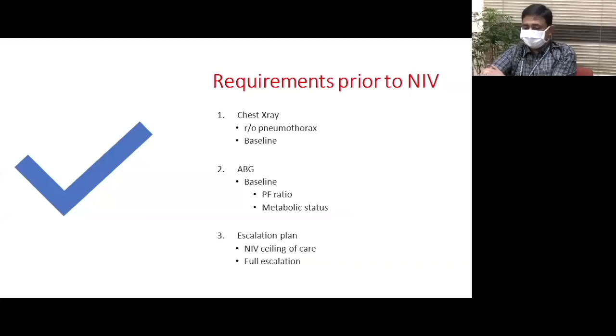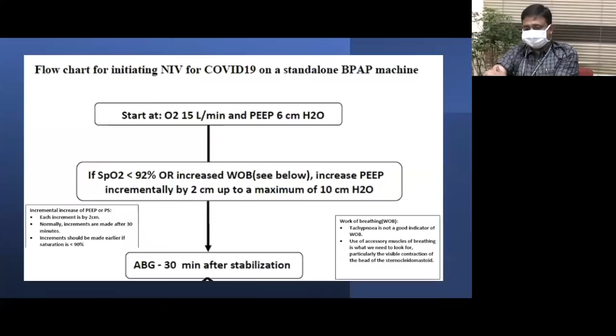This is a flowchart for a standalone BiPAP machine, which has been fine-tuned during the first wave of the pandemic. So we start with an initial flow of 15 liters per minute, because these patients come in with type 1 respiratory failure, with a PEEP of 6 to start with. The saturation target is 92 and a work of breathing which is settled. If these two are not achieved, one would incrementally increase PEEP by 2 centimeters every half an hour to reach a maximum of 10 centimeters. At whichever point the patient stabilizes, 30 minutes later, we would do an ABG.